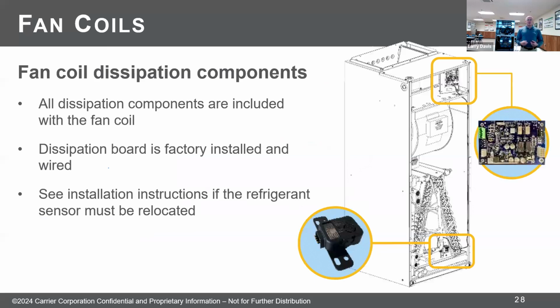Fan coils, the dissipation control that we've talked a little bit about already, it's going to come built into the fan coil already. Since the fan coil has the refrigerant coil already in it, that control is going to come in the coil pre-wired. The sensor that's there, we'll talk about it more as well. You may have to relocate that if you are putting that fan coil in a horizontal position. You will have to relocate it. There'll be instructions, and it'll show you exactly where to put that sensor.